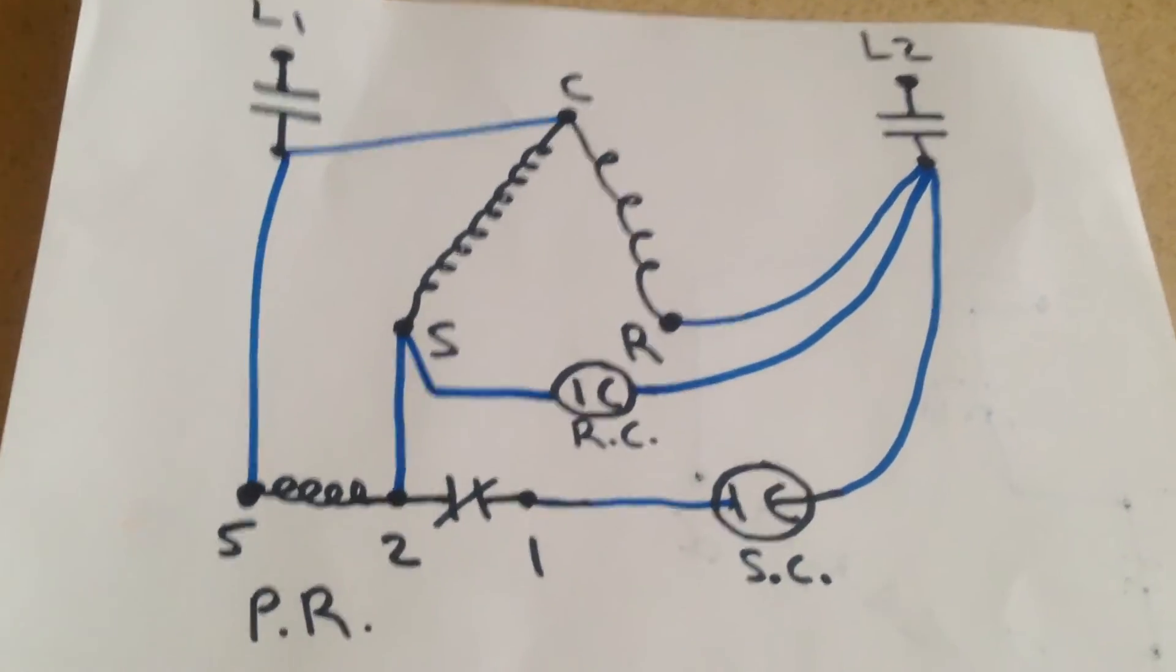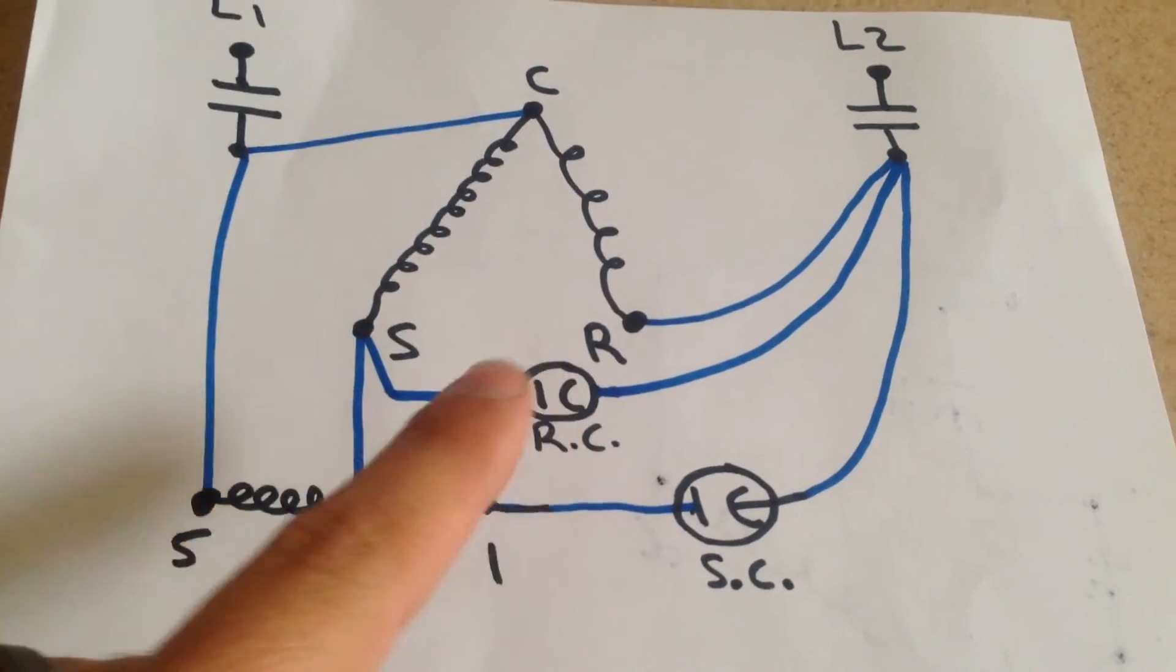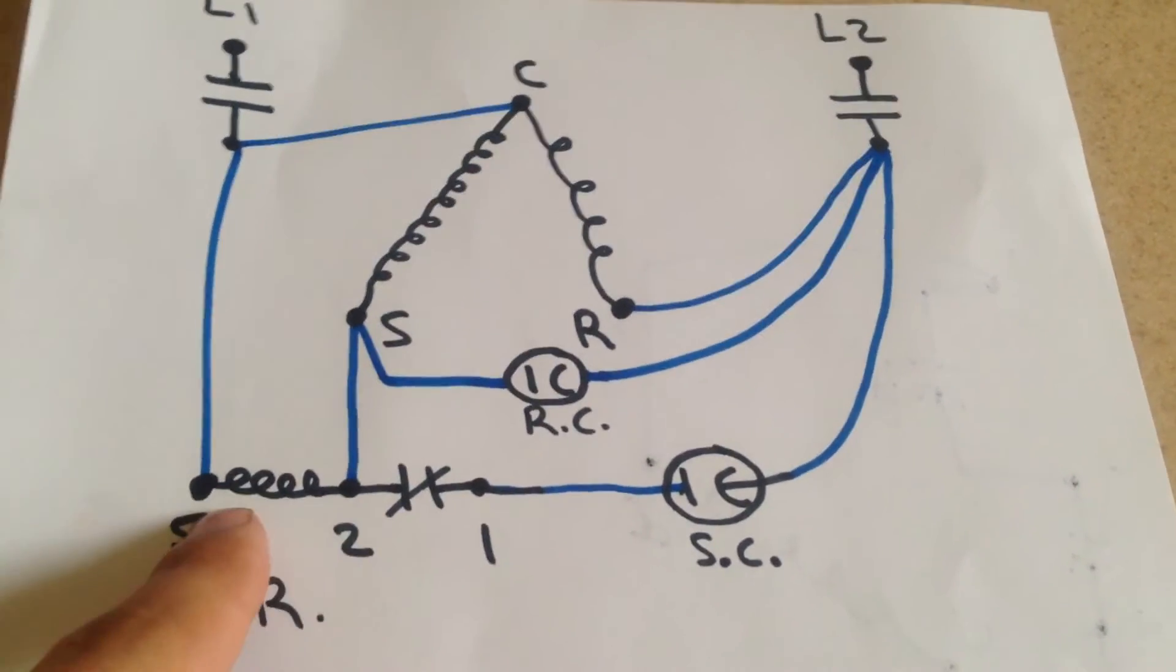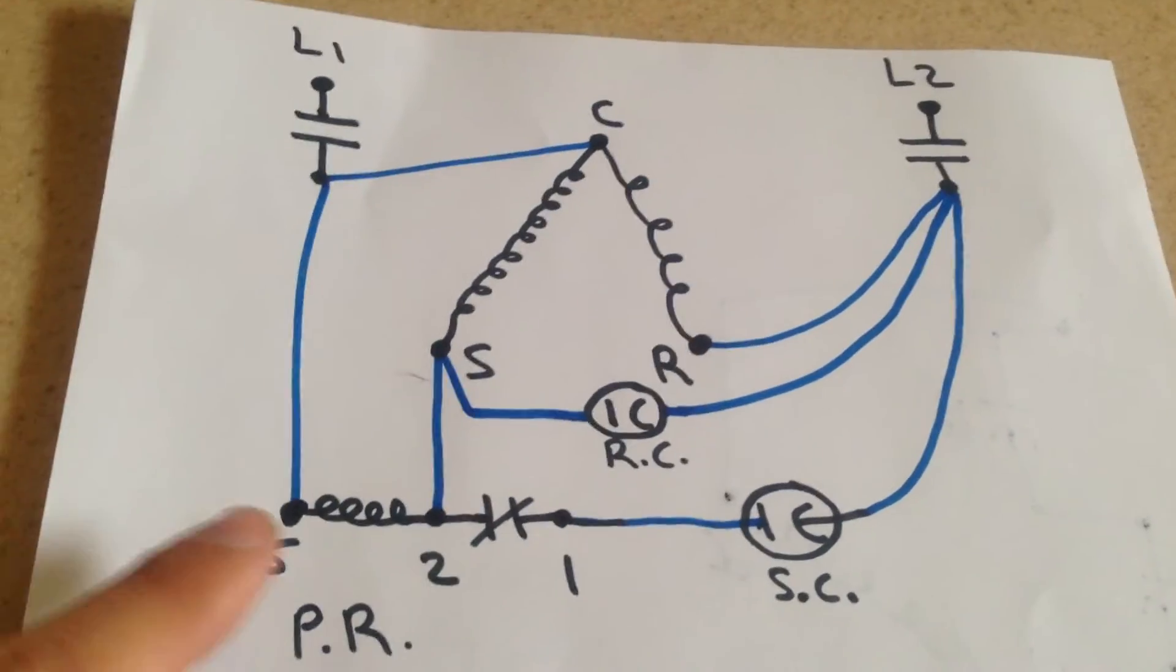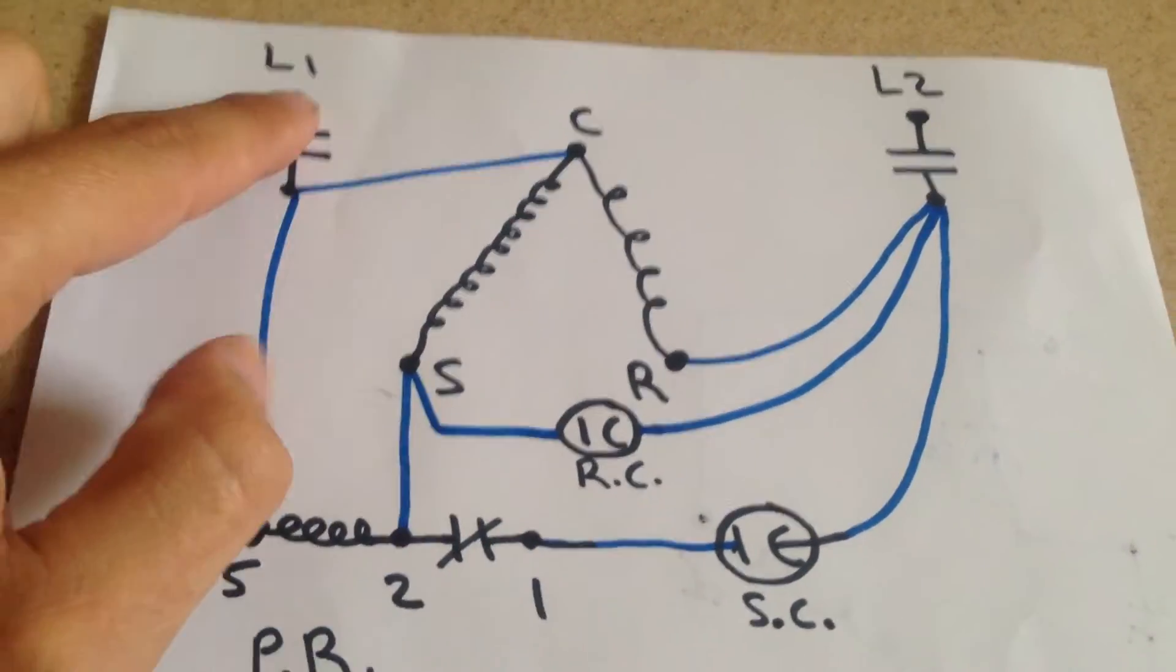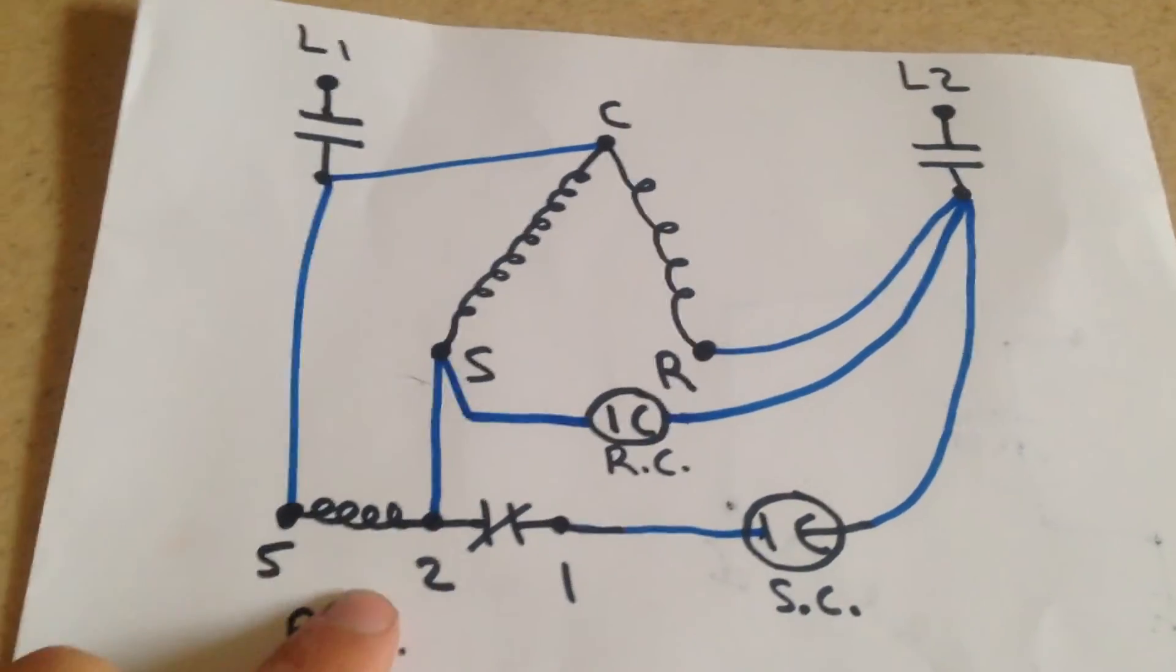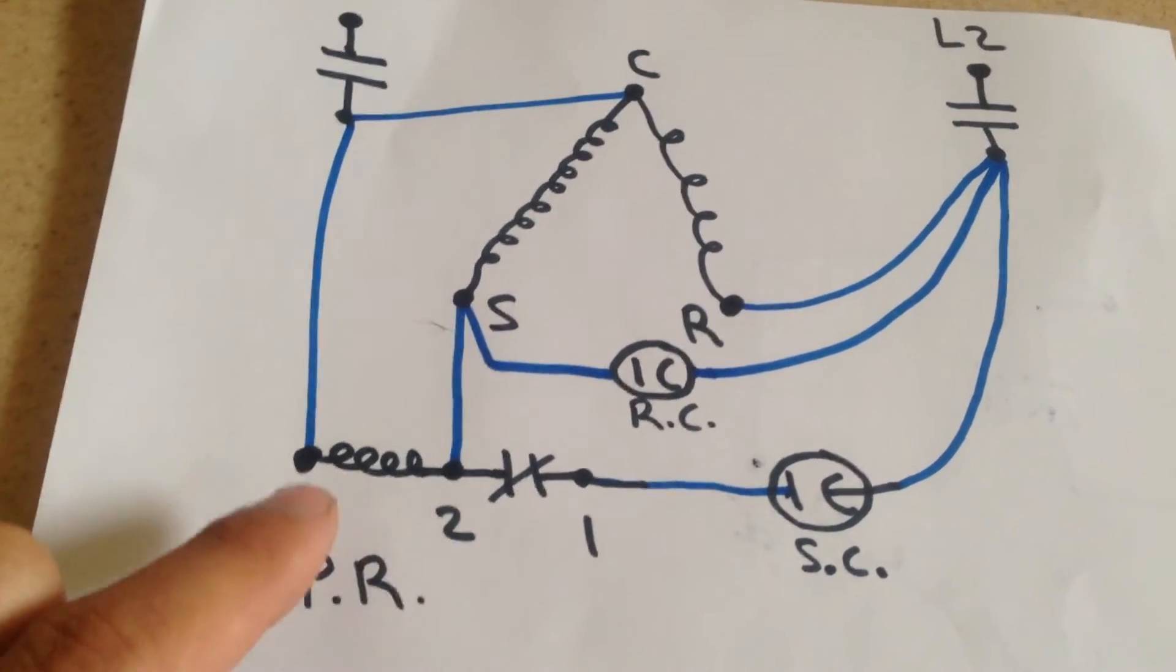So what that's going to do is assist our compressor on startup. And once it gets up to speed, this coil is going to sense a voltage across the start winding. And the reason it doesn't operate this contact initially when the contactor closes is because every coil or relay has a certain pull-in and drop-out voltage.